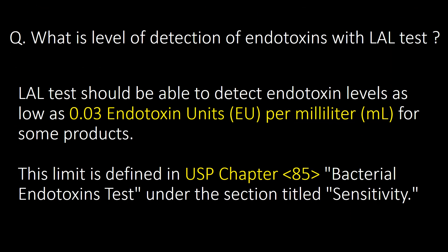What is the level of detection of endotoxins with the LAL test? The LAL test should be able to detect endotoxin levels as low as 0.03 endotoxin units (EU) per milliliter (mL) for some products.